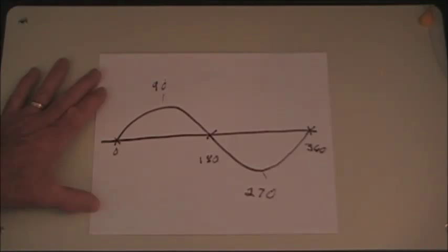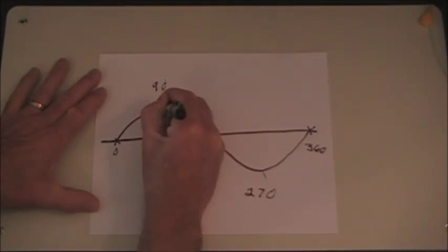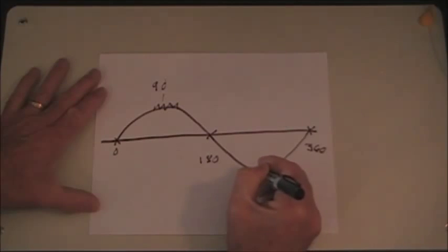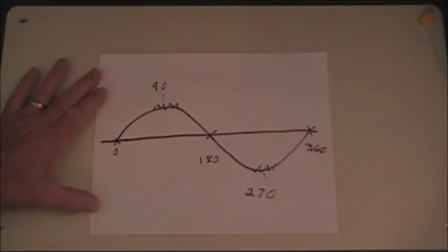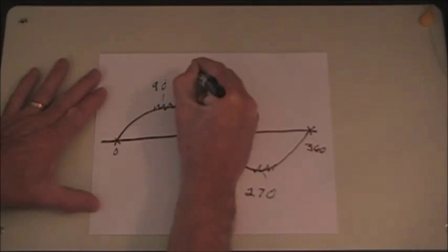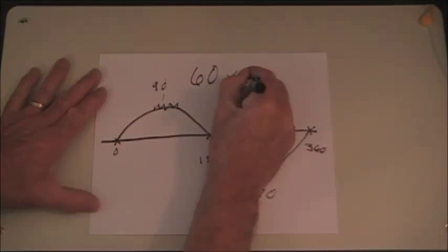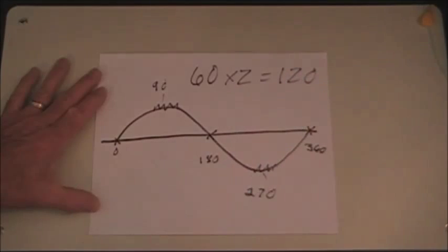They're going to arc at the high voltage points in the cycle. And basically there's two. There's a high voltage point here on the positive half of the cycle, and there's another high voltage point here on the negative half of the cycle. Both of those are at their maximum potential as compared to ground in one cycle of alternating current. So there's 2 arcs per cycle. If it's 60 cycle AC and there's 2 arcs per cycle, then there's going to be 120 arcs per second of alternating current. In other words, the frequency of the arc is going to be 120 hertz. Now, if we can match that to the frequency of the interference we're receiving, then that's a good indication that it's from a commercial power source.